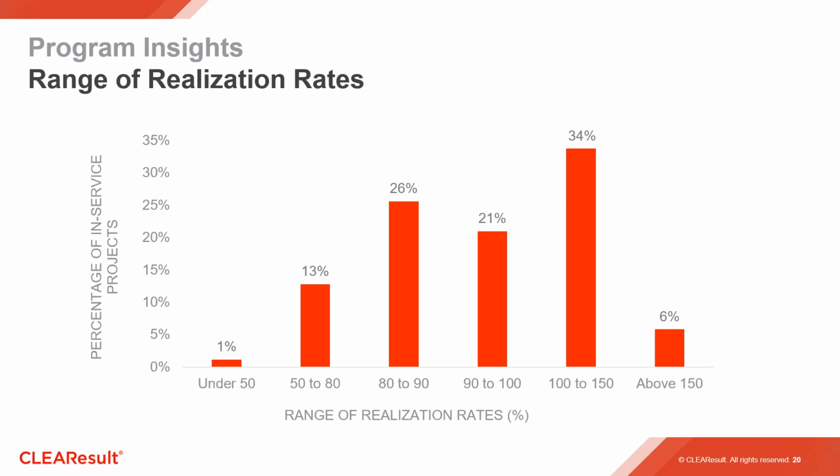Depending on the measure, we try to have more baseline data as opposed to less. But sometimes you have to really see what you can work with and do your uncertainty analysis, which is a big part of that. See how much the uncertainty of your baseline regression model would be with the data that you have.